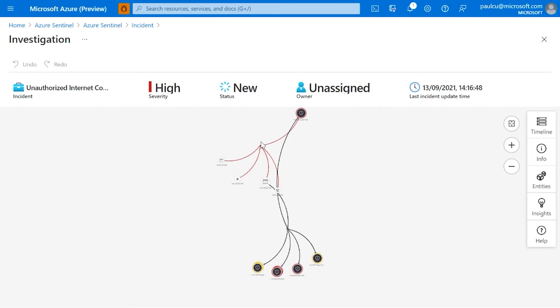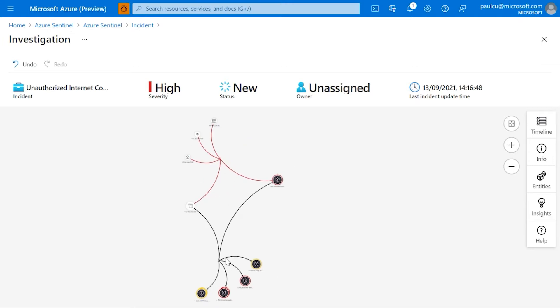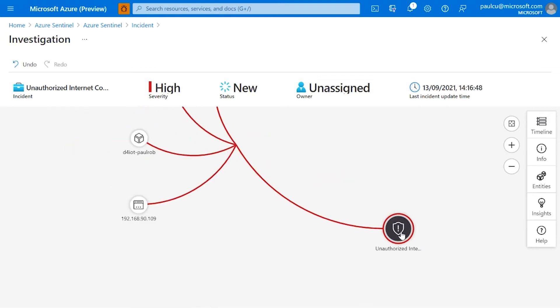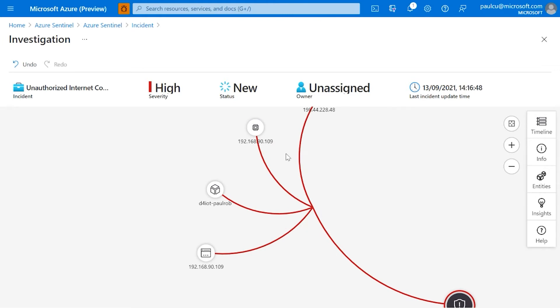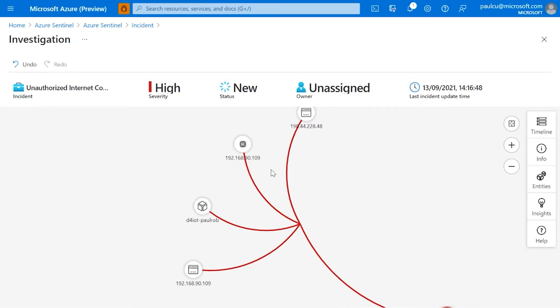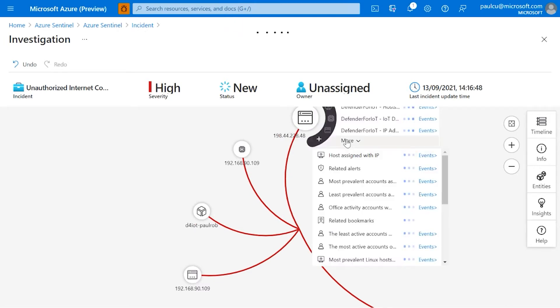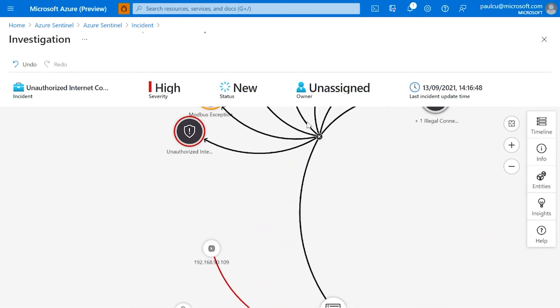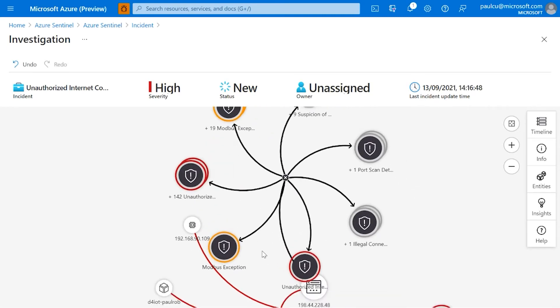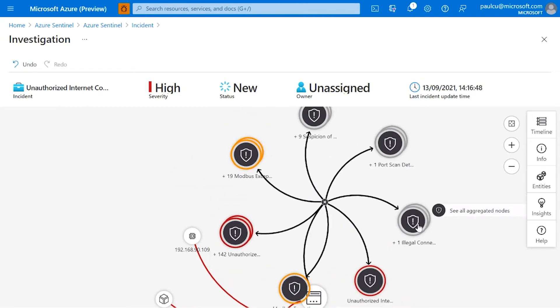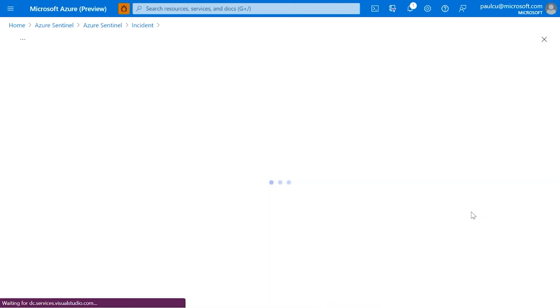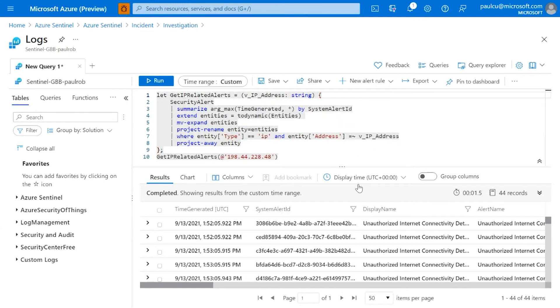This isn't going to work particularly well on the screen because I've got it set quite low resolution. Let's just get rid of that for the moment and zoom in a bit. So we can see unauthorized internet access is down here and then we've got some devices up here that have been involved in that particular alert type. Let's have a look. We've got the device. Let's see the sensor itself. Let's look at this and see our related alerts. And now we start seeing what else might have been happening. So we can see some port scans, some Modbus exceptions and other unauthorized types of activity.